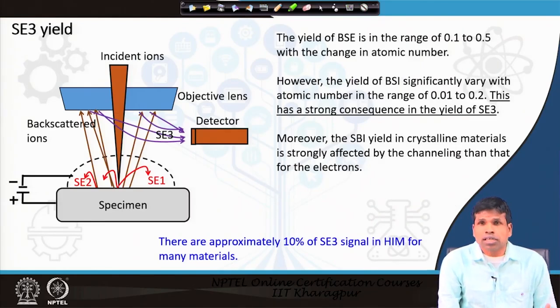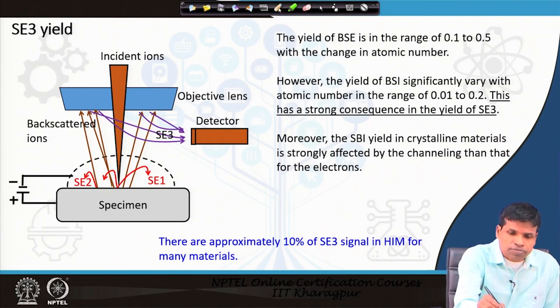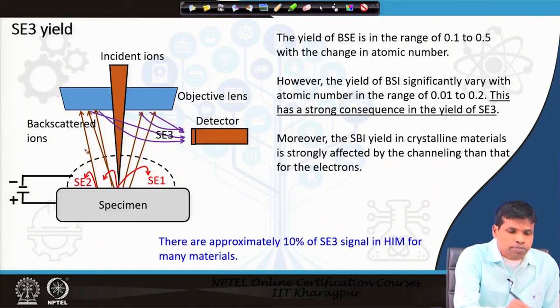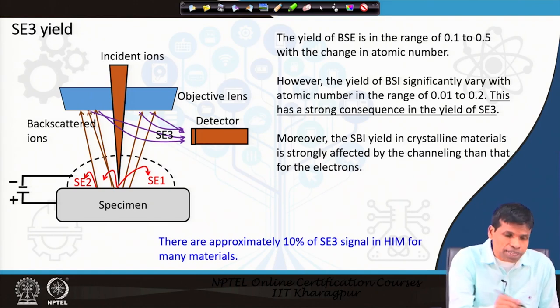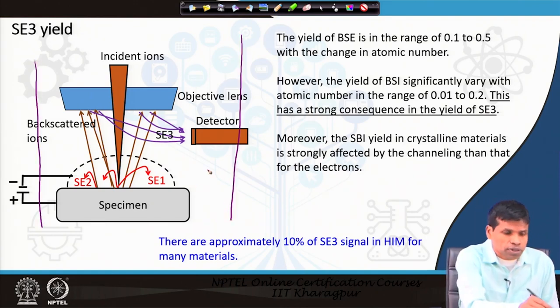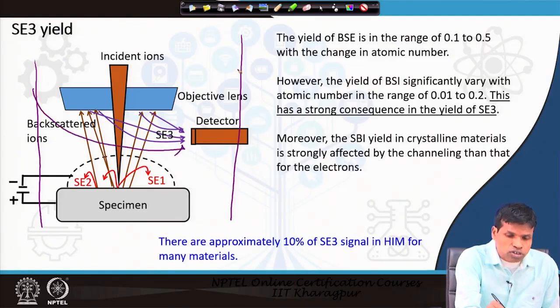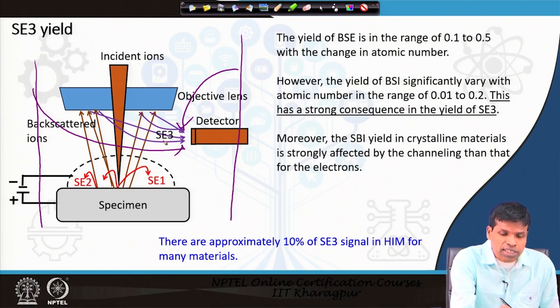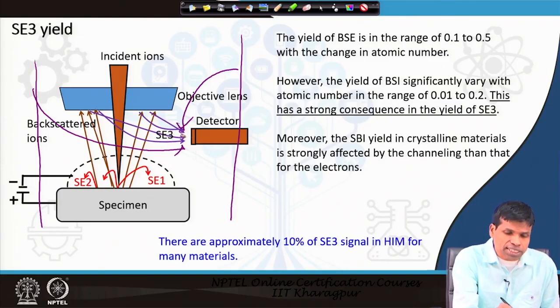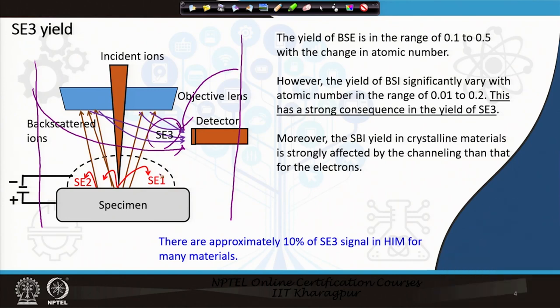There are also SE3 electrons, which we have discussed in scanning electron microscopy. Once backscattered electrons or backscattered ions come out of the specimen, they can strike the pole pieces or objective lens, or the wall of the chamber, and when they strike there they also produce secondary electrons. These are termed SE3 because their energy is again less than 50 eV. We can differentiate SE3 contribution from SE2 and SE1 by putting a grid around the sample.